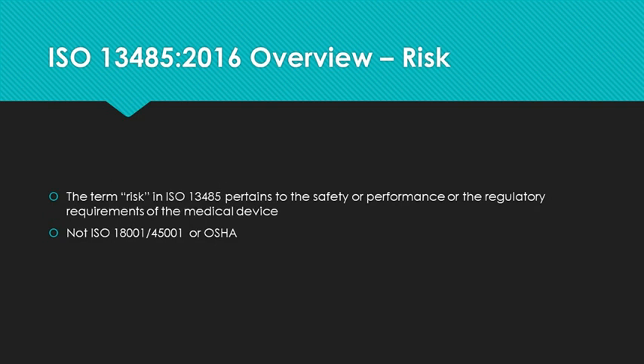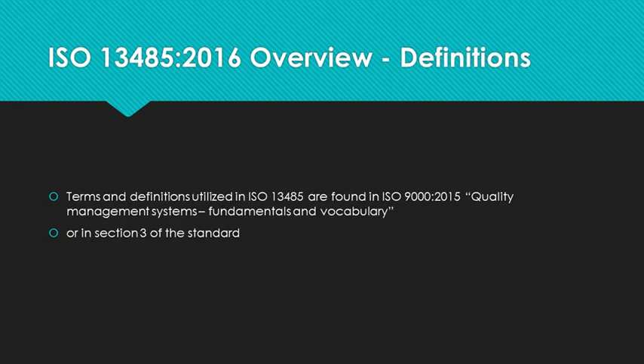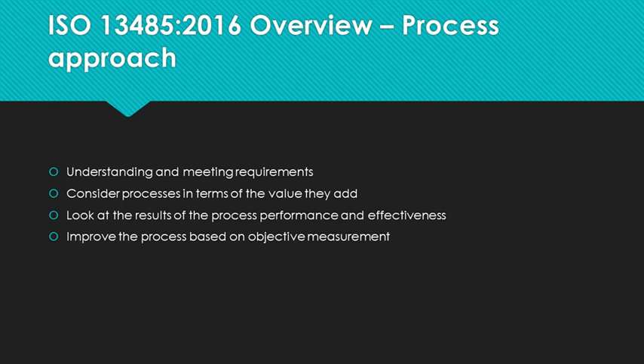The term risk in ISO 13485 pertains to the safety or performance or the regulatory requirements of the medical device. It is not talking about ISO 18001 or ISO 45001 or OSHA, but the risk of the device to the patient or user. Terms and definitions utilized in ISO 13485 are found in ISO 9000-2015, Quality Management Systems Fundamentals and Vocabulary, or in section 3 of the standard. A process approach must be utilized. It must emphasize understanding and meeting requirements, the value the processes add, the results of process performance and effectiveness, and improving processes based on objective measurements.